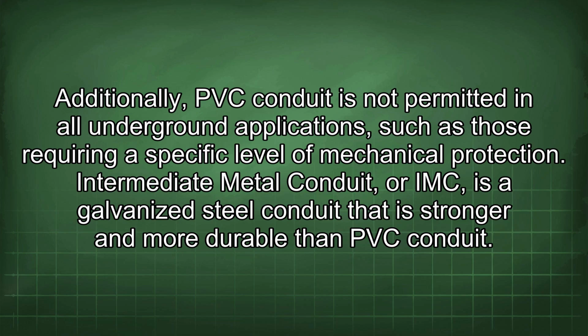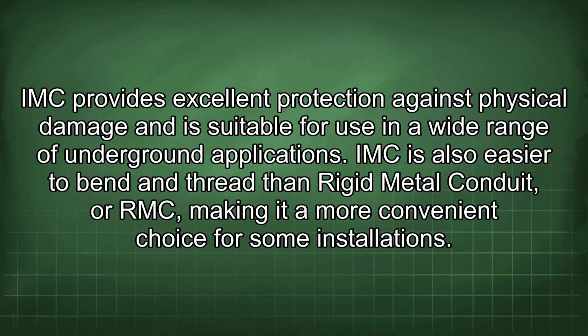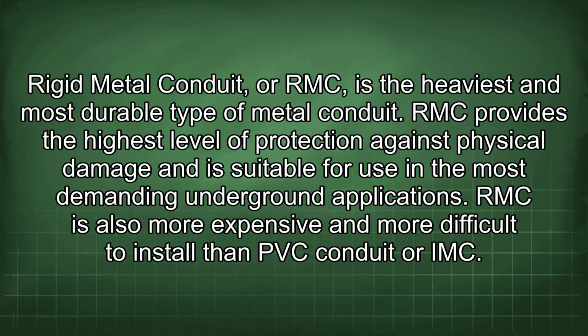Intermediate metal conduit, or IMC, is a galvanized steel conduit that is stronger and more durable than PVC conduit. IMC provides excellent protection against physical damage and is suitable for use in a wide range of underground applications. IMC is also easier to bend and thread than rigid metal conduit, or RMC, making it a more convenient choice for some installations. Rigid metal conduit, or RMC, is the heaviest and most durable type of metal conduit. RMC provides the highest level of protection against physical damage and is suitable for use in the most demanding underground applications. RMC is also more expensive and more difficult to install than PVC conduit or IMC.